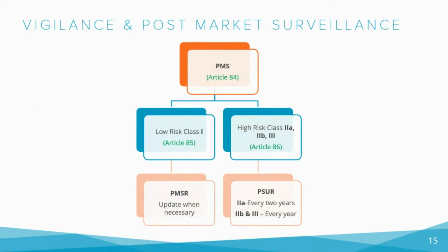Now coming to PMS. The MDR places a significant focus on post-market surveillance and vigilance throughout the entire life cycle of medical devices. This means that after a device has been placed on the market, it must be continuously monitored for any adverse events or problems that may arise. To ensure that manufacturers meet the requirements of the MDR, they must have a PMS system in place to collect and analyze data on the performance of their devices.